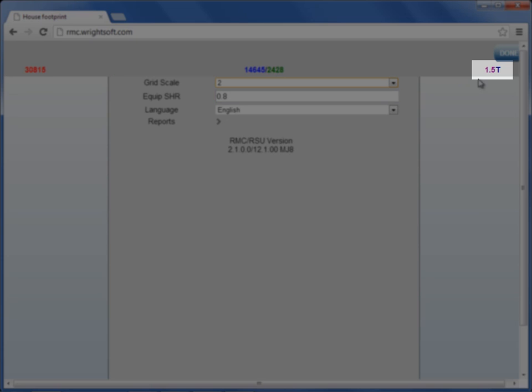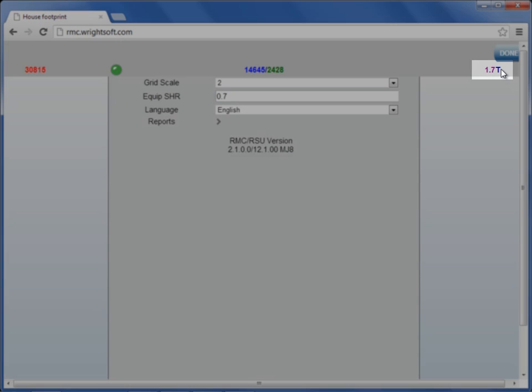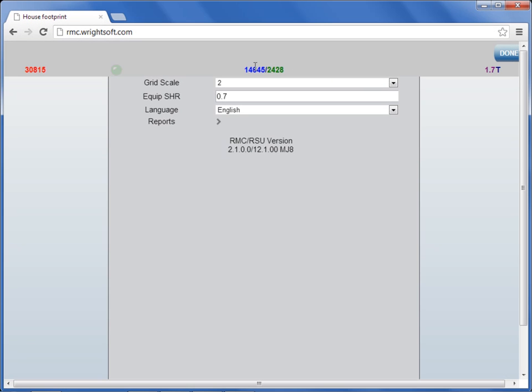It went from 1.7 to 1.5 when we changed the equipment sensible heat ratio from 0.7 to 0.8. If we change this back to 0.7, the total tonnage will change again. The sensible load and the latent load remain the same. It's the target tonnage that adjusts when you change the equipment sensible heat ratio.